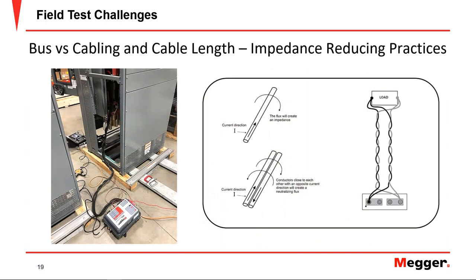Again, the objective when we talk about connections is to minimize the impedance. So here are some recommendations to minimize that impedance, especially when testing towards the limits of what the SPI can give, which is 2000 amps. There are certain things we can do to get the highest current possible. First, we can use conductors in parallel, two or more cables in parallel. The shorter the cable, the better, right? Again, to minimize the impedance, as well as increasing the gauge, or in other words, using thicker conductors.